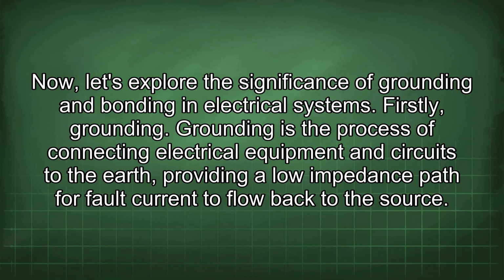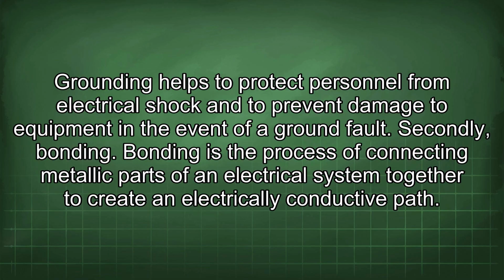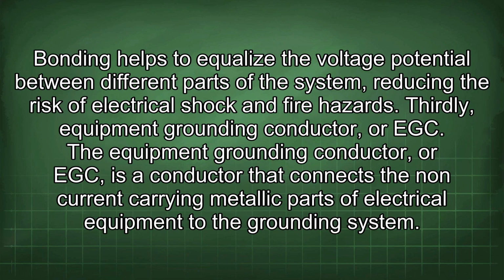Firstly, grounding. Grounding is the process of connecting electrical equipment and circuits to the earth, providing a low impedance path for fault current to flow back to the source. Grounding helps to protect personnel from electrical shock and to prevent damage to equipment in the event of a ground fault. Secondly, bonding. Bonding is the process of connecting metallic parts of an electrical system together to create an electrically conductive path. Bonding helps to equalize the voltage potential between different parts of the system, reducing the risk of electrical shock and fire hazards.